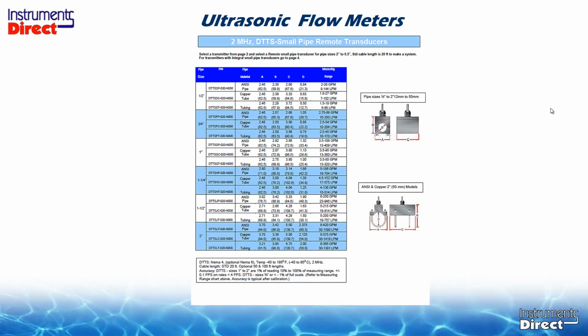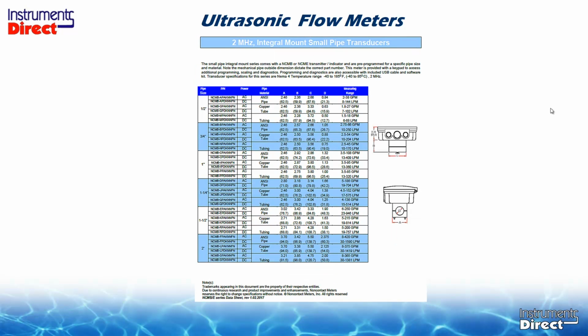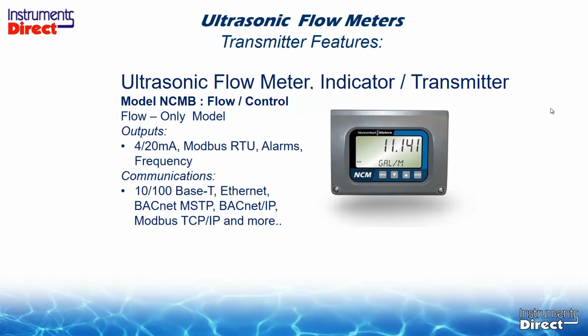The sensor diameter and crystal spacing is prefixed. So as you can see, it comes in a whole bunch of different sizes, and this makes the installation of the small pipe sensor very simple. You just open up the two parts and clamp it together, and you're all set to go. No spacing adjustments required. Now the meter comes in two basic models.